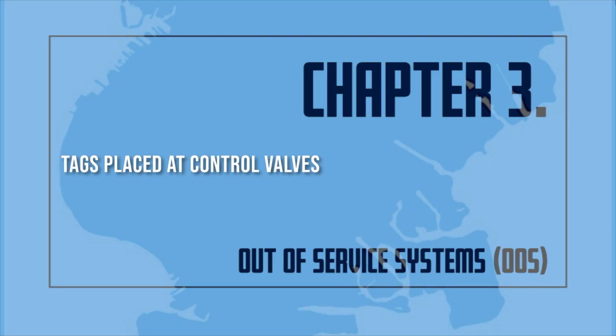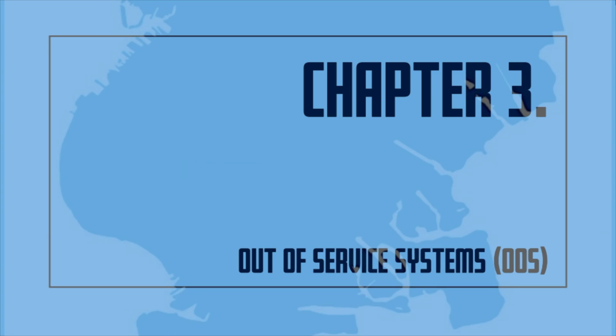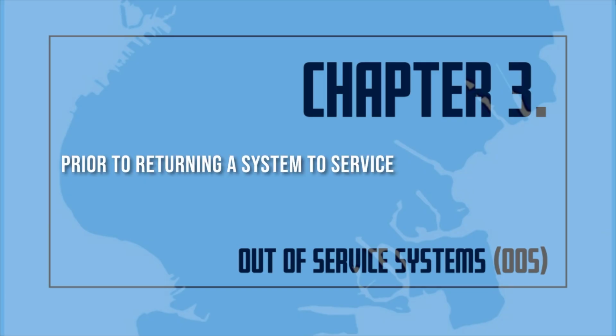For systems that are fully or partially out of service that are not equipped with fire department connections, the appropriate tag shall be placed at the main control valve. The fire department is to be notified immediately. Prior to returning a system to service, the impairment coordinator shall ensure that the necessary tests and inspections are conducted, the system is operating normally, the fire department borough dispatcher is notified, the building owner's tenants in the affected area are notified, the insurance carrier is notified, the emergency preparedness staff are notified, the central station operator, if so equipped, is notified, and that the out-of-service tags and discs are removed.